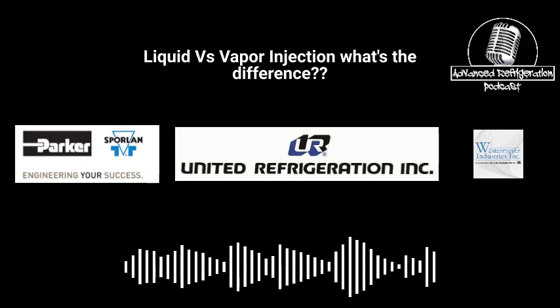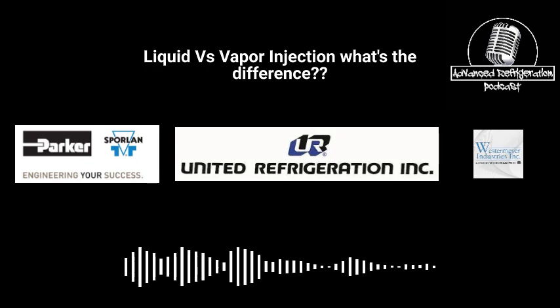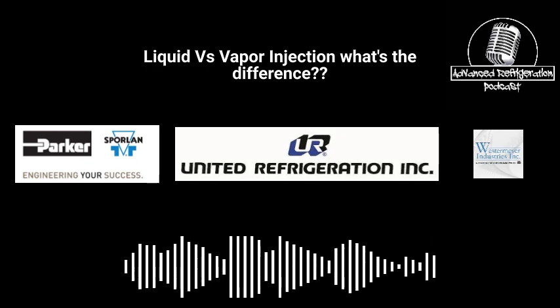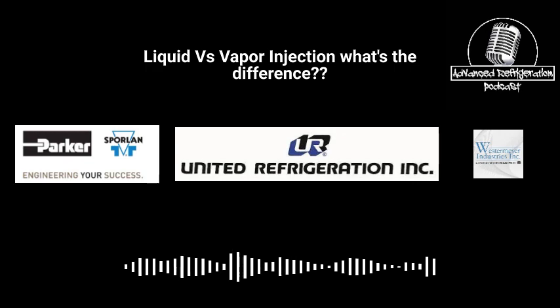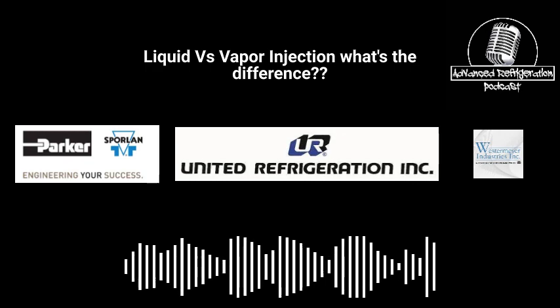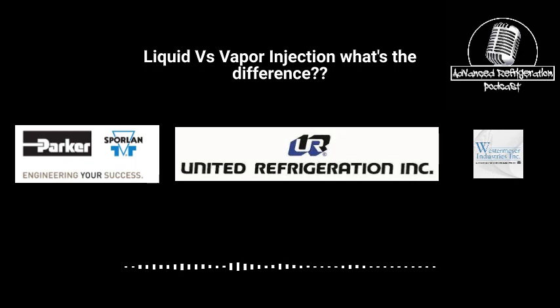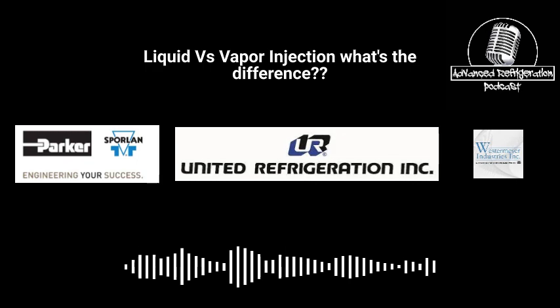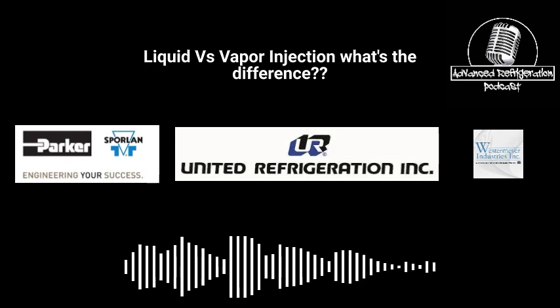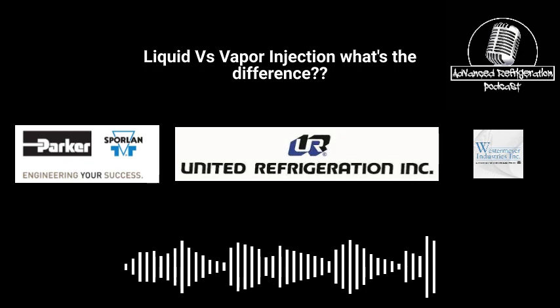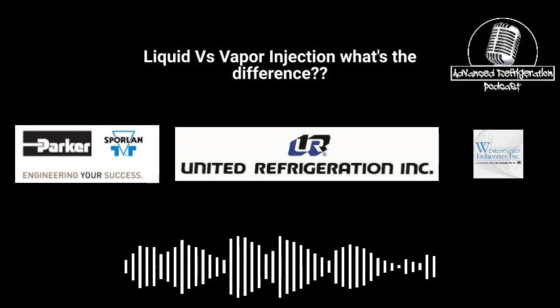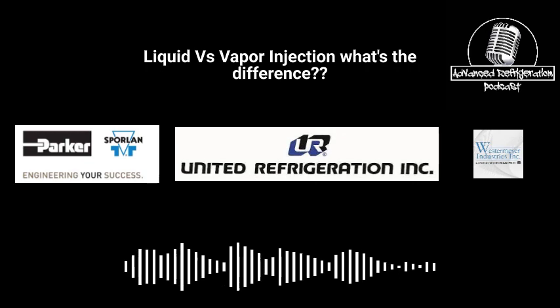Yeah, while you're bringing up that part, I've seen guys screw up and accidentally get a liquid injection compressor when it was supposed to be a vapor, because the supply house gave them the wrong compressor. And if you look at them, there are some non-vapor injection compressors that are liquid injection that have a rotor lock on there. So just because it has a rotor lock fitting doesn't mean anything. So you need to verify it with the model number. Now especially if it's a Copeland, super easy. Just click on your Copeland mobile app, scan the old compressor, and look for compressor replacements, and make sure that compressor is a replacement. And if you're questioning the new one, look and see if it's a vapor injected compressor. Like Brett said, it has the V in there.